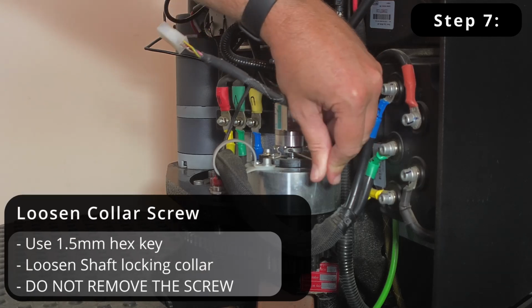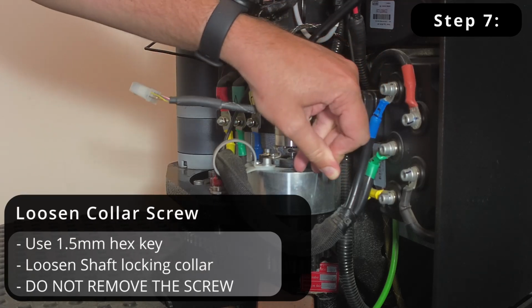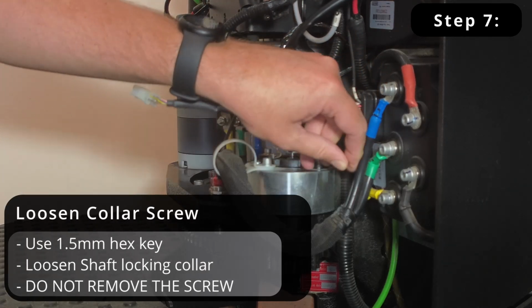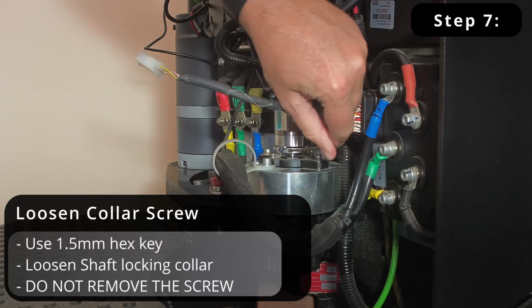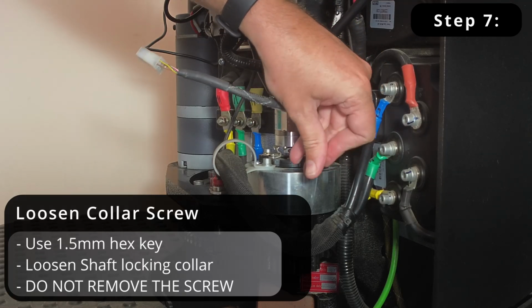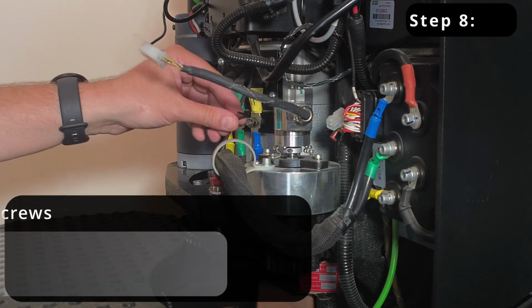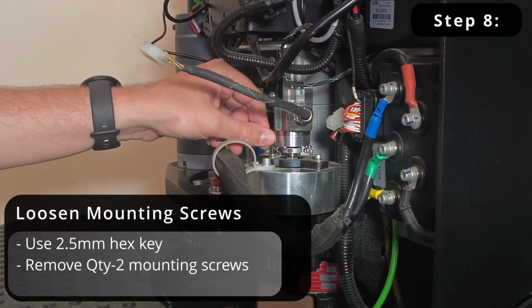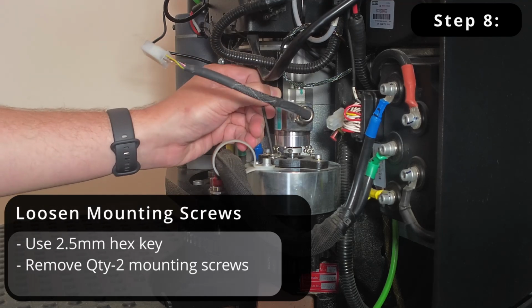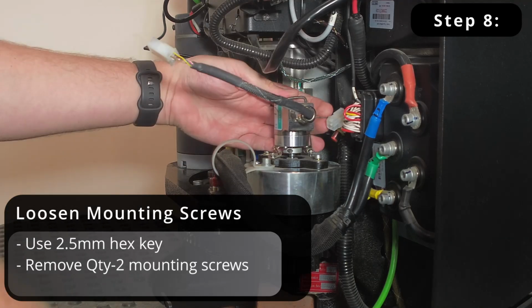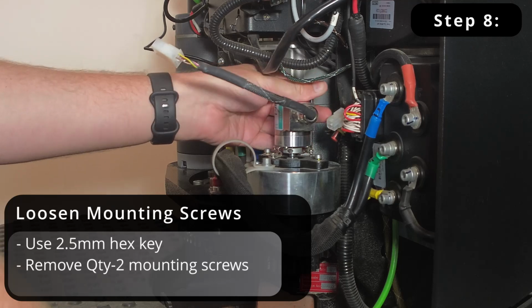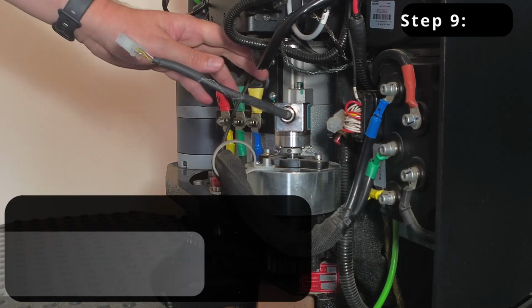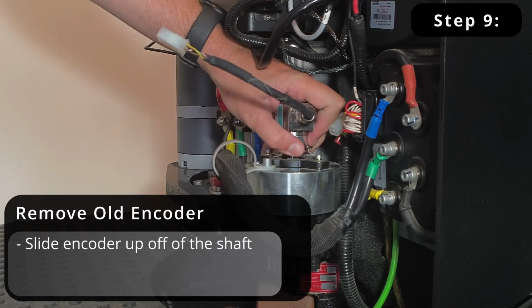Using the 1.5mm hex key, loosen the collar screw on the bottom end of the encoder, just above the bearing block. Do not remove the screw completely. With the 2.5mm hex key, remove the two screws securing the encoder mounting tabs to the bearing block. Slide the encoder off the shaft.